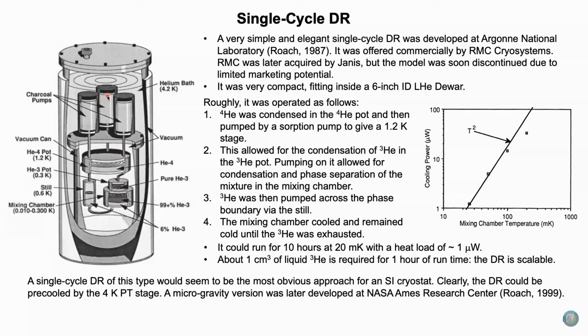So the mixing chamber, along with the still, has its own charcoal pump. The charcoal pump for the condenser, one for the helium-4 pot, and one for the, it's called the still here, which is where you pump out the helium-3 from the mixing chamber. So once you get everything condensed, you start pumping on the mixing chamber, rather on the still, and that will cool. This particular model ran for 10 hours at 20 millikelvin with a heat load of 1 microwatt, which is really good.